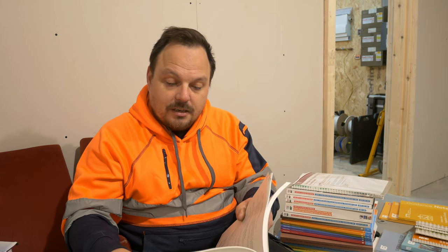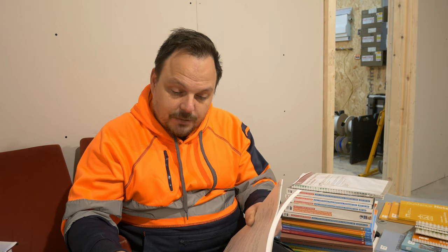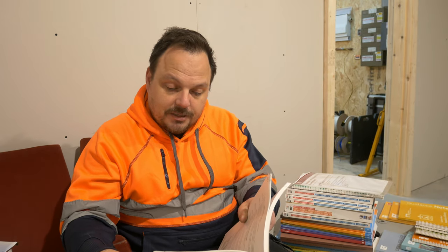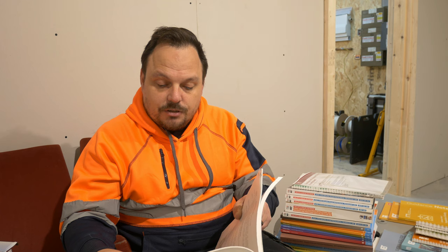There's electrical equipment such as your mineral insulated cables without an overall PVC covering laid on it. So it says exposed conductive parts of cables such as copper sheathed or mineral insulated cables are required to be connected to the MET of the installation, so your main earthing terminal, by a CPC designed to conduct earth fault currents. The cable tray or basket to which the sheathed mineral insulated cable is attached or may be in contact is not itself an exposed conductive part and therefore does not require earthing. To do so would only serve to distribute further any touch voltage resulting from an earth fault on an item of equipment to which the cable was connected.